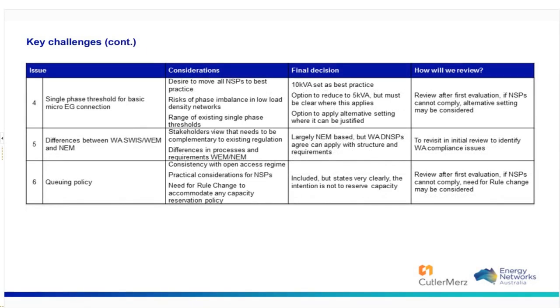Issue number 4, and I think I did talk about this one earlier, but the concept of the single phase threshold for the basic micro embedded generation connection. So we initially said that the single phase should be set at 10 kVA because, when we looked across all the NSPs, that tended to be the best practice. The move towards 10 kVA was considered best practice. That was our initial scan. And we had a strong desire that these guidelines should be pushing network service providers to be connecting larger systems, to potentially not be necessarily risk averse when those risks weren't necessarily likely to manifest. So if one network could accommodate 10 kVA on single phase, why couldn't another?